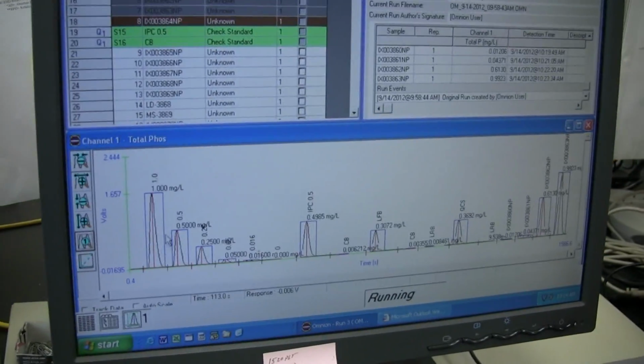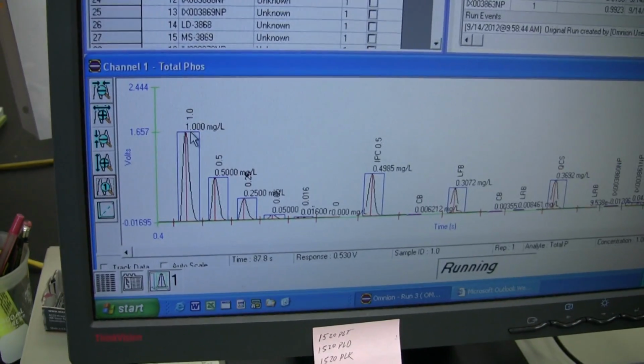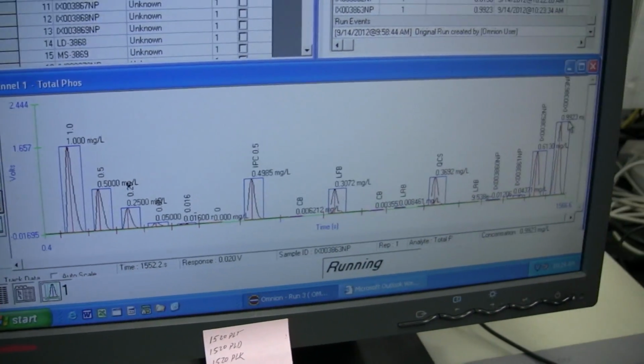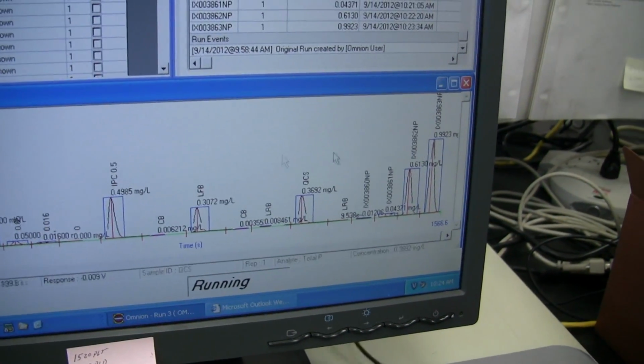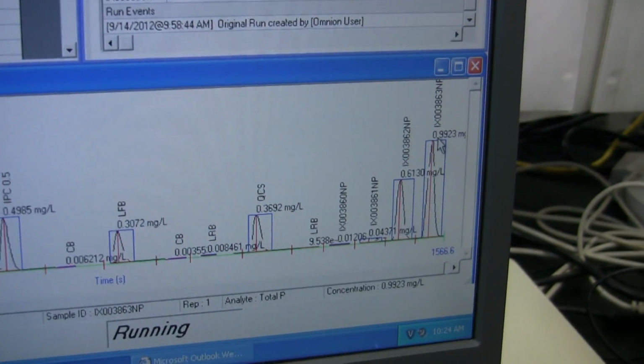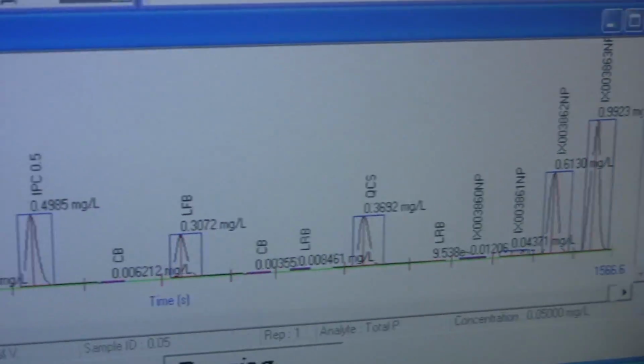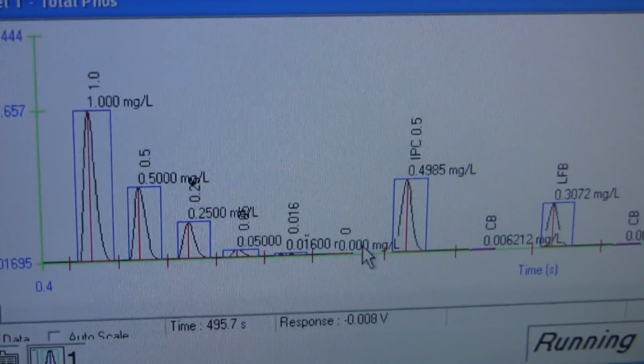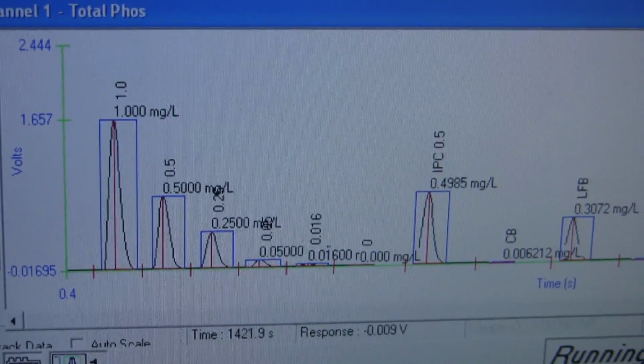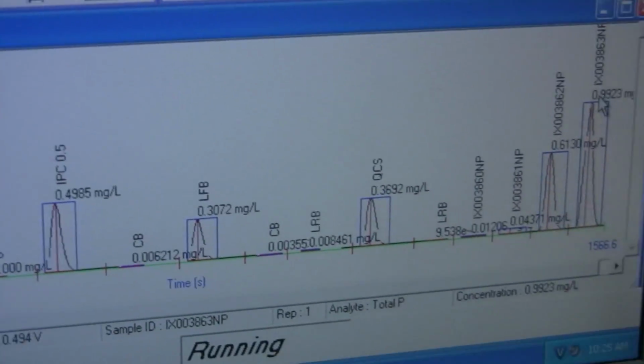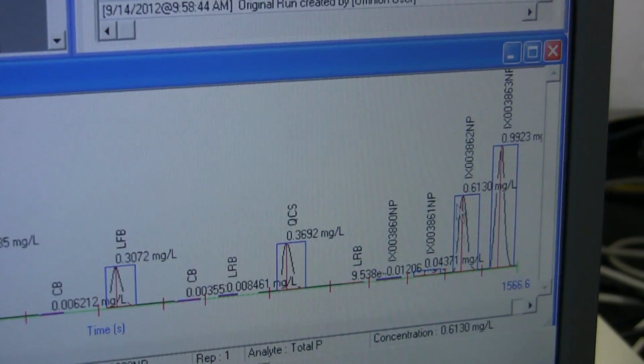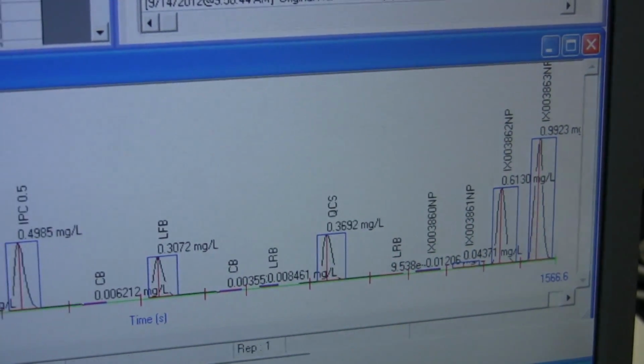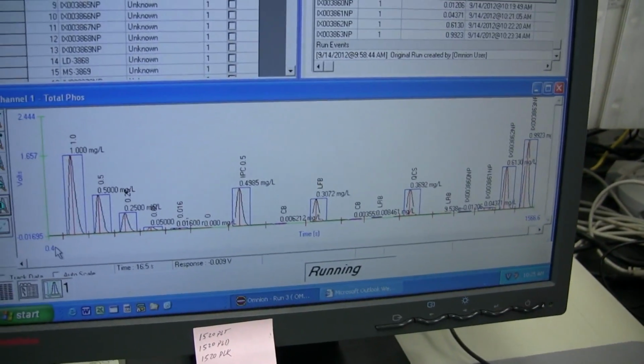So here, that's my 1 standard. If I look at the height of this, it was very close. I said it's going to be real close, but it looks just a little shorter. And it turned out to be 0.99, so I can take that number because it's within my calibration range. My calibration range is from 0 to 1.0. If this would have been 1.2, I would have had to do a dilution and then run it again so it was within my calibration range.